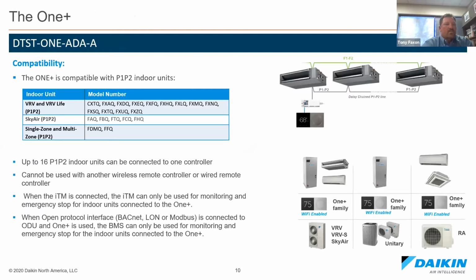One of the things you've got to look at with the One+ is it's a primary only controller. So you cannot use a second controller on the same fan coil or group of fan coils. When used with a commercial application where the ITM front end is used, the One+ will do all of the controlling and the ITM will monitor only. Similarly, if connecting via BACnet, LonWorks, or Modbus, the building front end would only be able to monitor.